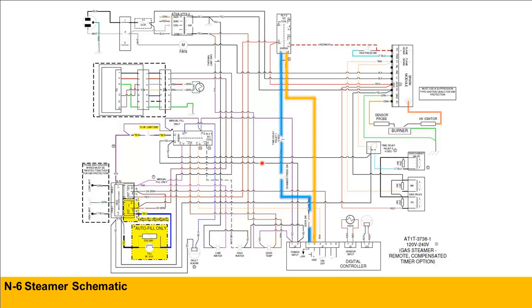At this point we know we have power coming across. We've tested all of our components, and so the next step would be actually removing the blue and orange wire, or as depicted, removing the 2 wires off the DC relay and see if we have 24 volts across the 2 wires. Now, if we have the 24 volts and the relay is not energizing, then we have a defective relay. Now, let's say the relay is energizing, but we still have no power transfer from the red to red and white. That means we have a defective contact within the relay. But either way, it's a defective relay.